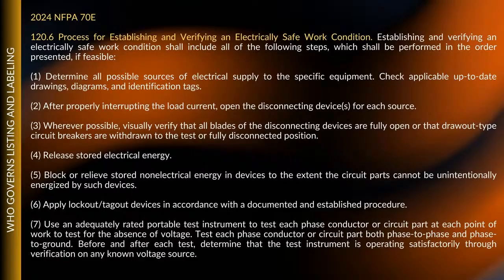The other thing I've commonly seen where they fail on this lockout tagout program is they lock out the genset, but they don't make it electrically safe. You basically have to disconnect everything from your genset, because if you just lock out the control, the ATS, then you're not in an electrically safe work condition, because that genset could start inadvertently while you're working on it. So you have to make sure that battery backup or generator backup is fully locked out and tagged out correctly so it cannot backfeed that system. That's just two cases where I see lockout tagout failures.